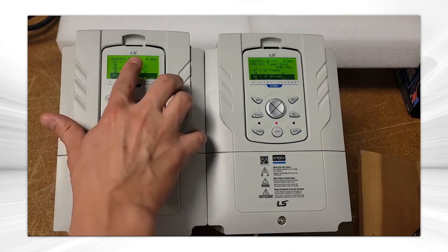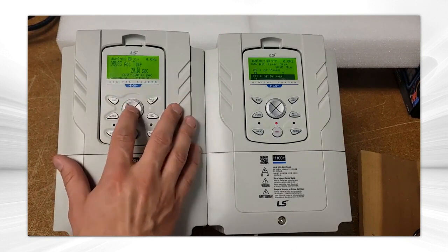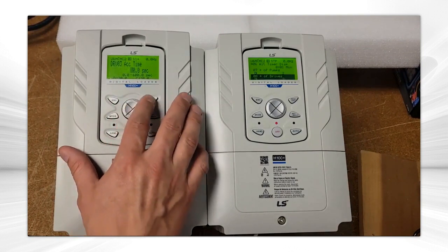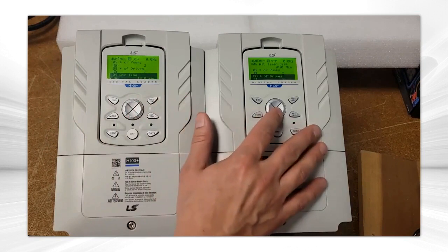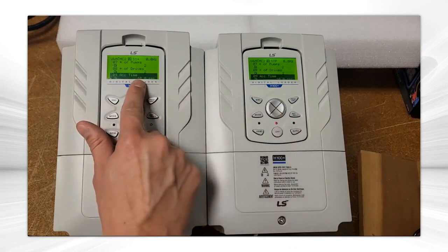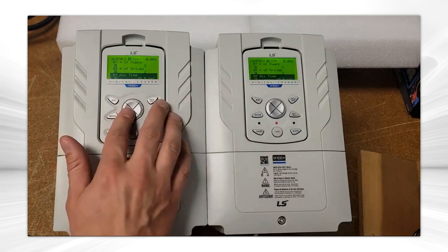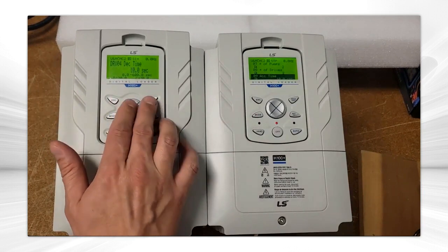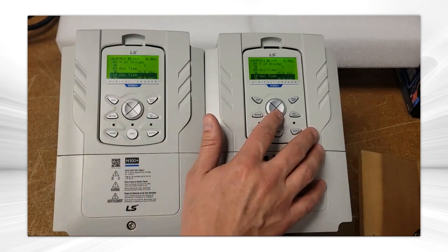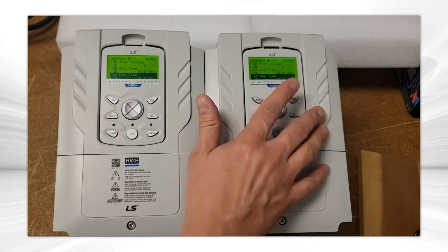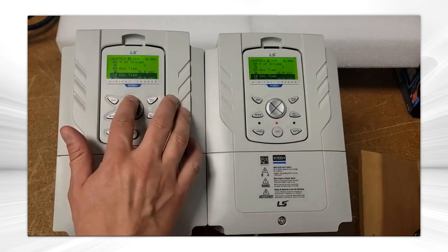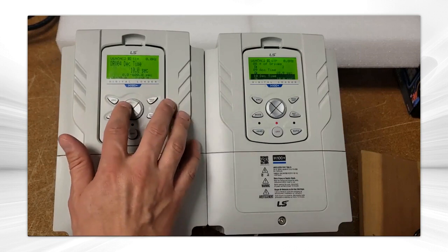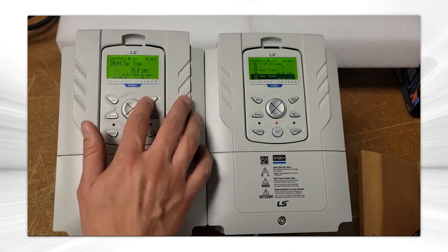So actually this drive is the lead drive, so I believe Acc time might be one that does a share. Yeah, so I changed this to 10. It automatically adjusted that one to 10. Just to show that again, I'm going to set my decel time to 10. Now I can see that that's at 10. So it wrote from one drive to another, so it shortens up your startup.